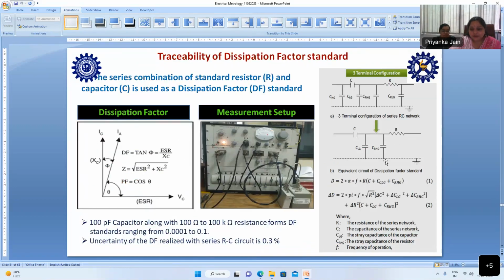For traceability of dissipation factor, we have recently established the dissipation factor in terms of capacitance and resistance standards. The series RC combination is used to define the dissipation factor standard. We have the GR1620 bridge, which we use to define dissipation factor standards, and we are capable of measuring dissipation factor in the range of 0.0001 to 0.1. This is a unitless quantity, and the uncertainty of the dissipation factor is in the order of a few percent, a fraction of a percent. So this is the basic circuit science behind the dissipation factor. You can see that the tan delta dissipation factor is the effective series resistance upon X. From this we are deriving these circuits.